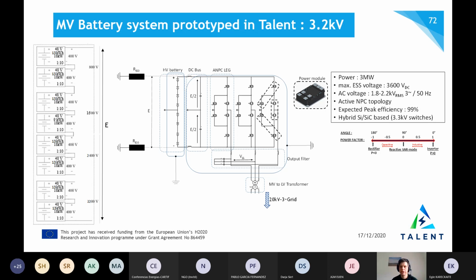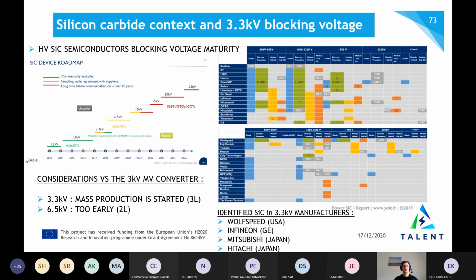With this topology, you can work in inverter mode, so with a unity power factor, or rectifier, of course, with a -1 power factor, or at 0 for support to the grid, like pure reactive power to the grid, or intermediate power factor. You can go to other power factors that are not unity or 0.